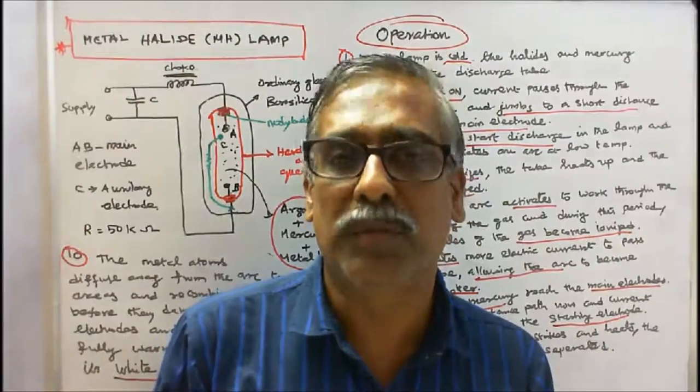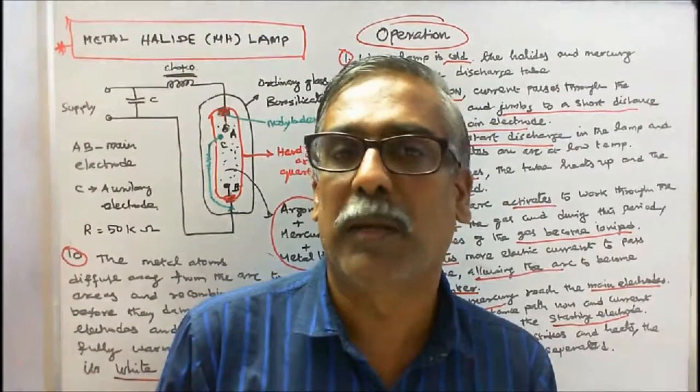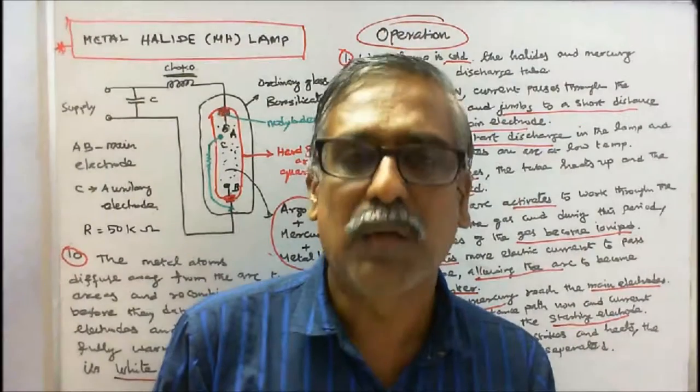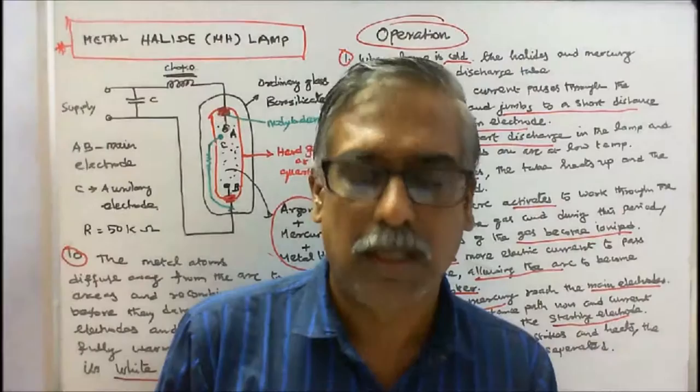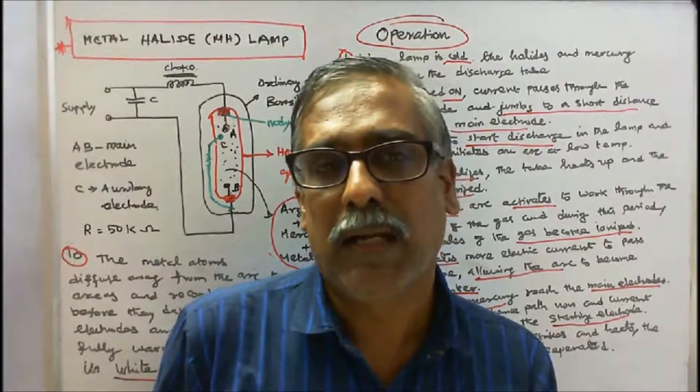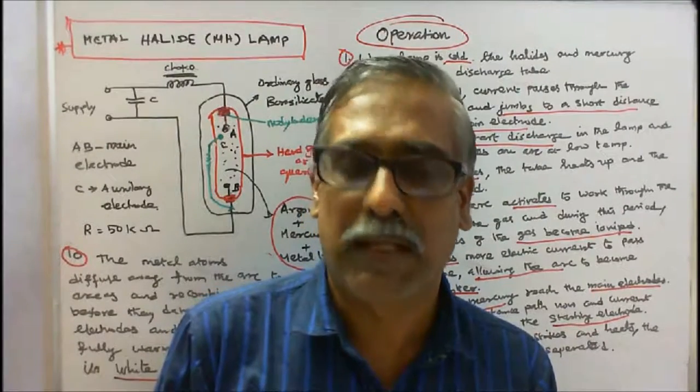4. Lifetime is 20,000 hours for mounted base up and 10,000 hours for horizontal mounted lamps. 5. Color rendering index is 60 to 90.